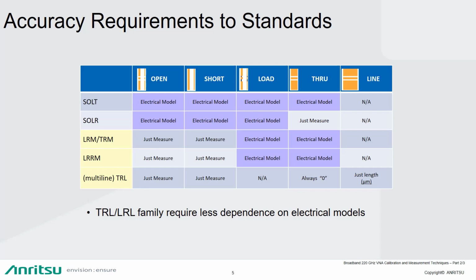So again, going back to the SOLT method, that requires accurate definition of equivalent impedances of the open, short, and load standards, and it requires a precise model of the through standard across the entire frequency range of the measurement. So this can be very challenging, especially as we get up into the millimeter and sub-millimeter wave frequencies, and that's again why this method is typically limited to the 40 to 70 gigahertz range.